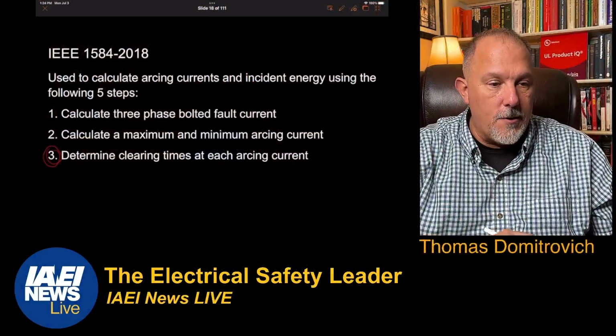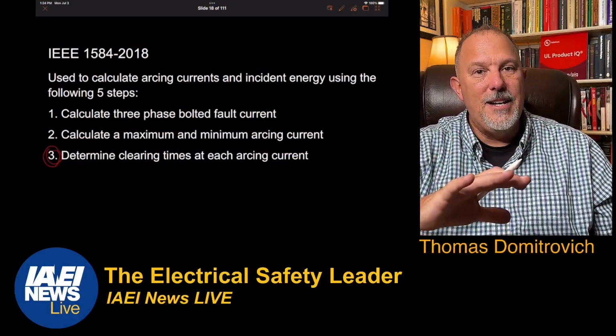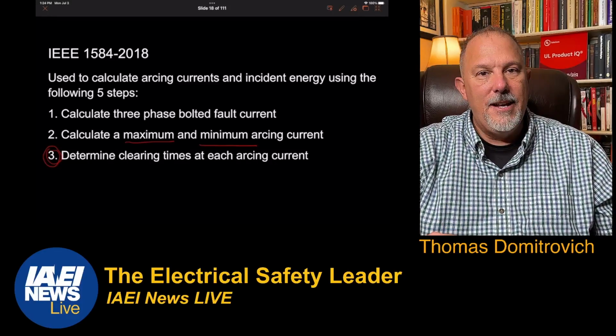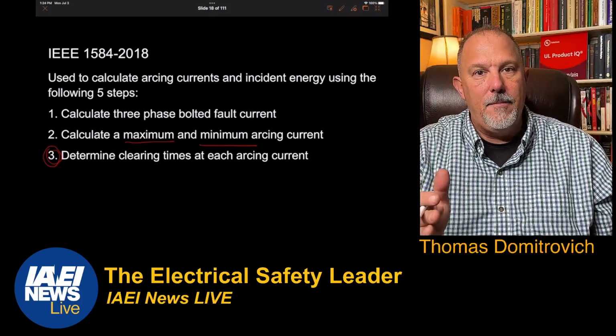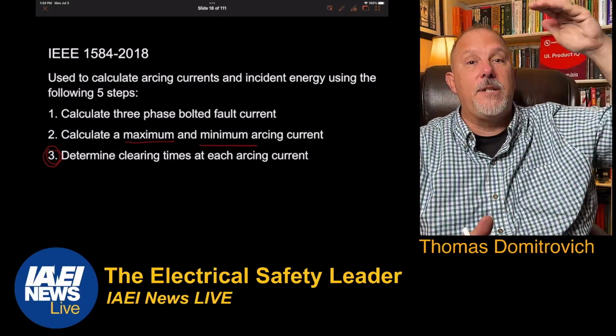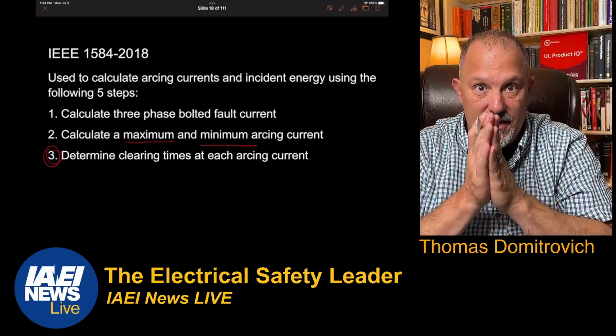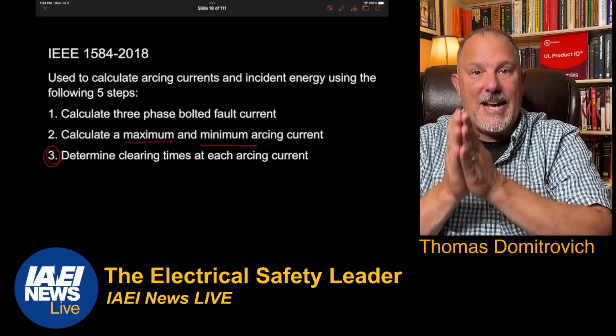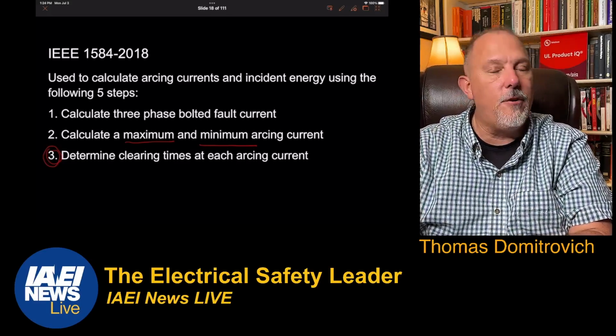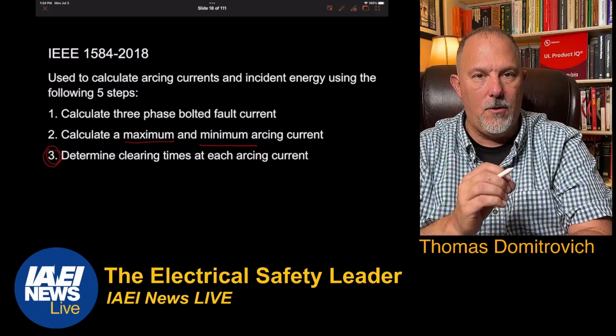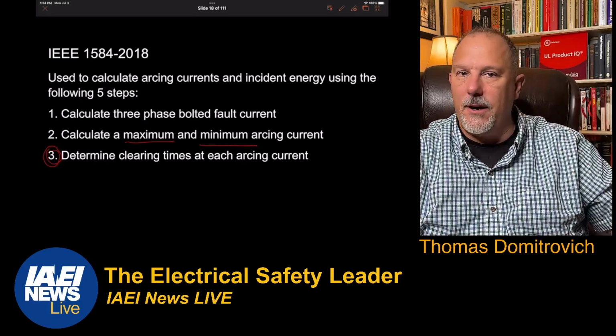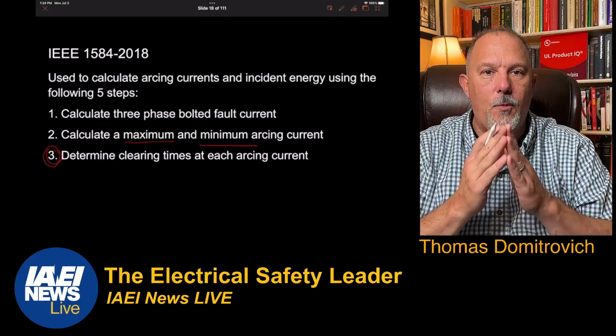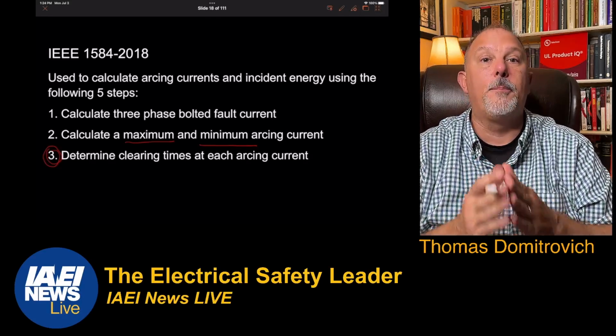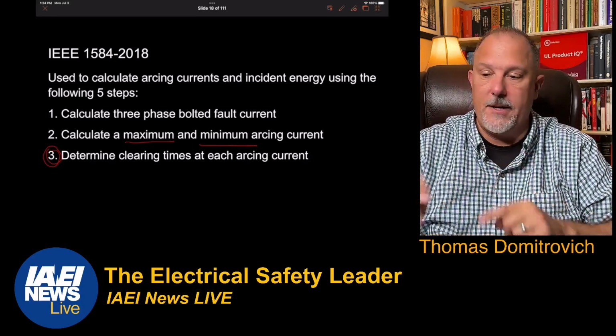So step 3 in this whole picture is to determine the clearing times. Now I have to take my maximum and minimum arcing currents and analyze them with respect to the clearing time of the protecting overcurrent protective device. So we have to understand that fundamental as well, that the amount of time that I let an arcing current flow will be dependent upon what we call, it's not in 1584, it's not in 70E, it's not in the National Electrical Code, but we call this overcurrent device the protecting overcurrent device. I'll explain to you why that's significant in a second.